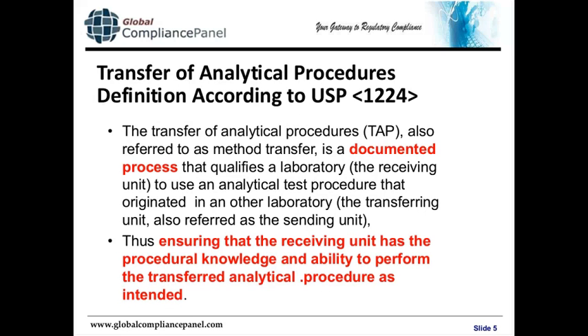This slide shows the definition of the transfer of analytical procedures from USP 1224, which is the chapter we are discussing today. Most important here are the words 'documented process.' The process should ensure that the receiving unit has the procedural knowledge and ability to perform the analytical procedure as intended. The key points are that the receiving laboratory is qualified to use the transferred method and consistently gets the same results as the transferring laboratory, day in and day out.